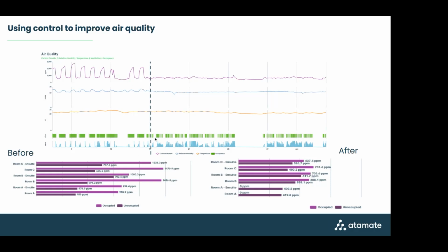By controlling the fans based on air quality, you can see we've significantly improved the air quality in that building. Over 2,000 parts per million isn't a great level of CO2. On average it's dropped from around 1,000 parts, or a bit higher, to about 600 parts per million - significant savings. Of course, that potentially comes with a cost, because we're putting more air through the building, and that air needs to be conditioned, either heated or cooled depending on time of year. So just be aware there's a bit more to it.